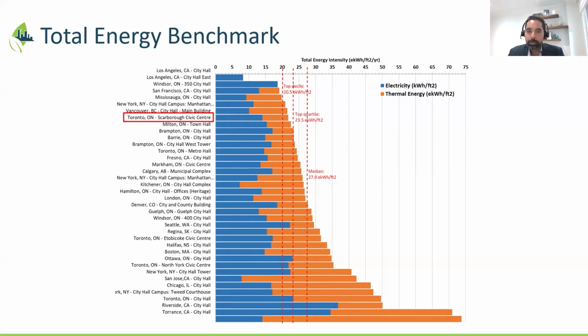So this to me is kind of a challenging situation. You would put a fault detection diagnostic services provider and the software itself to work on a building that's already efficient, already below the top quartile target, and target that building to achieve savings on that. It tells you how the application of the software, and how it got implemented, resulted in these additional savings.